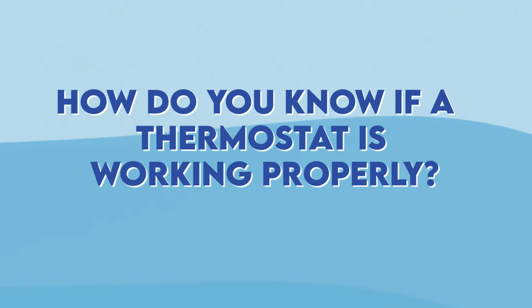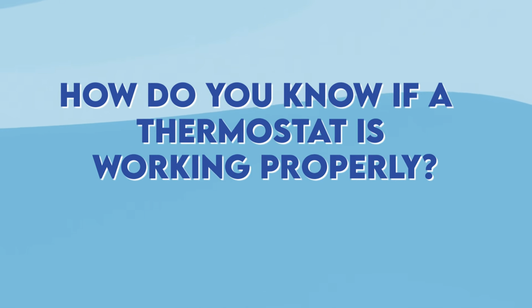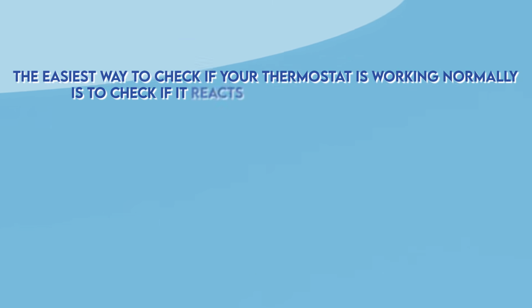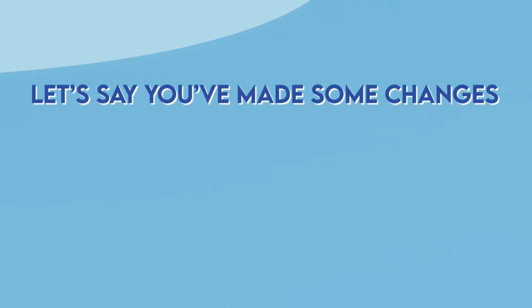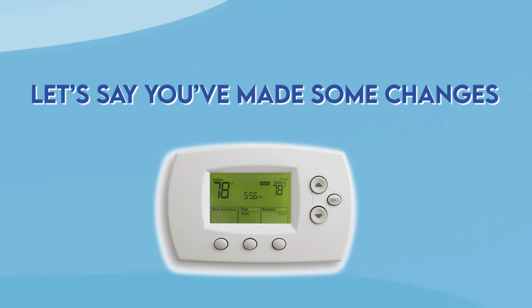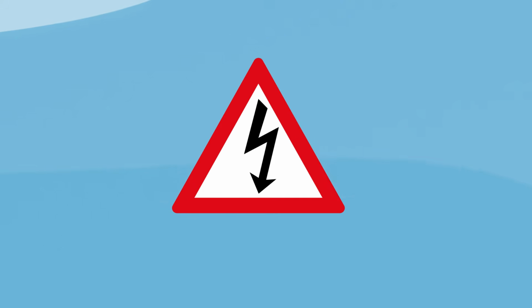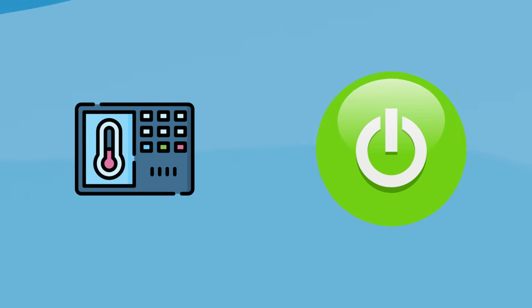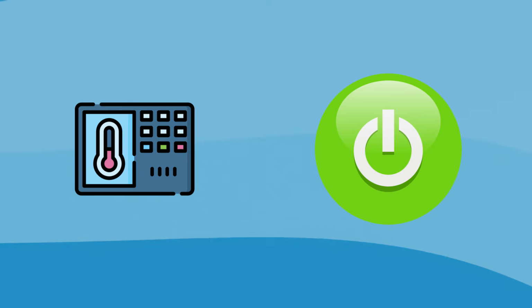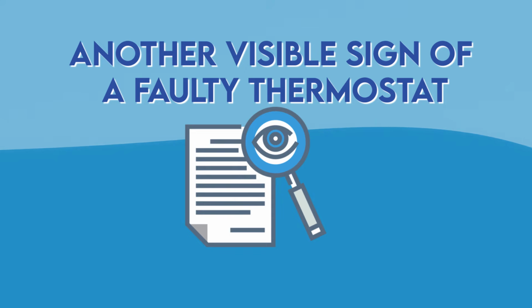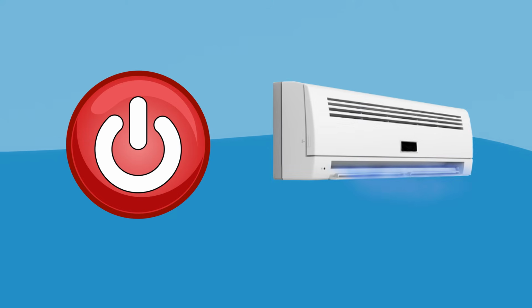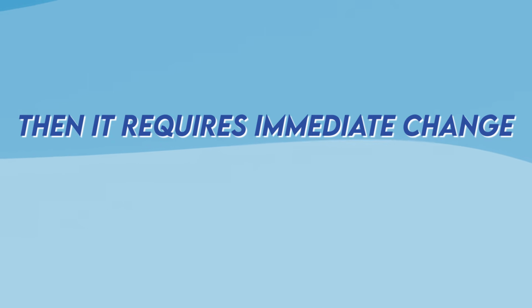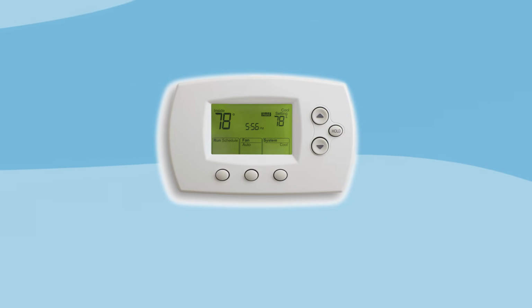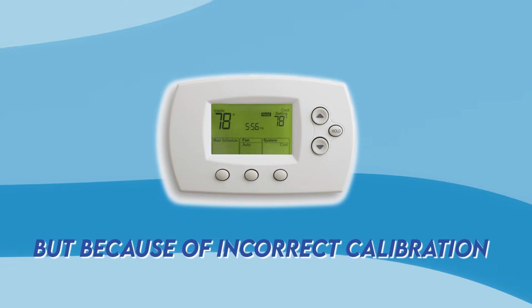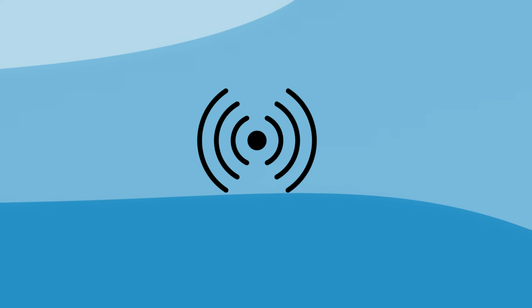Okay, but how do you know if a thermostat is working properly once you've done the fixes? The easiest way is to actually check if it reacts to any changes immediately. Let's say you've made some changes on the thermostat, and if it doesn't apply them immediately, it's most likely faulty. Also, faulty thermostats can't turn on your AC or furnace. Another visible sign of a faulty thermostat is if you turn off your AC and it still keeps working, then it requires immediate change. This doesn't happen simply because of a thermostat, but because of incorrect calibration, broken sensors, and bad wiring.